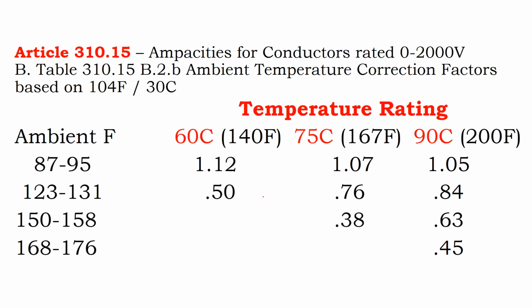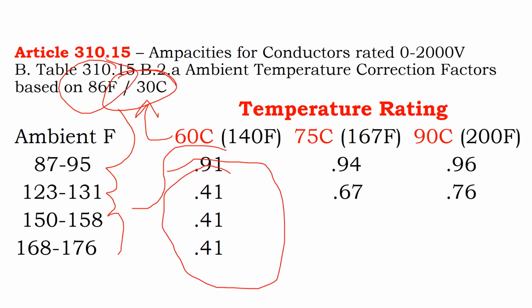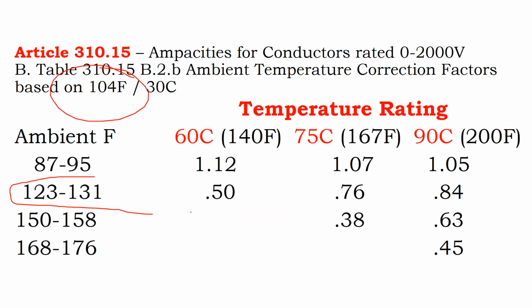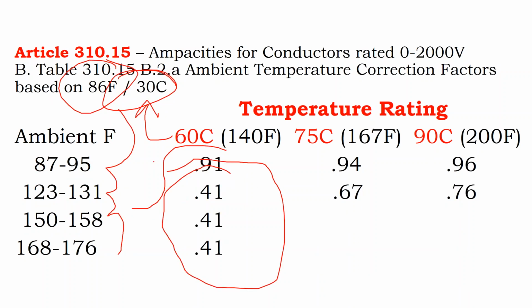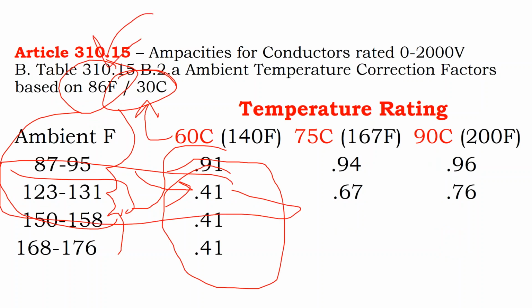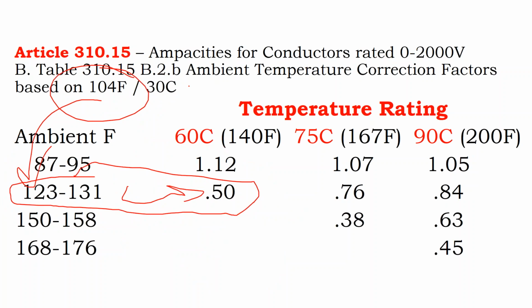Then we have the next table, and it's the exact same chart, but the only difference is it's done at 104 degrees ambient instead of 86 degrees ambient. So if you're trying to correct it for your actual ambient, now we're a little bit above it, and we have to derate the ampacity by 50%, whereas if we were doing our calculation based off a lower ambient, we would be derating it by 40%. The important thing is that you're being consistent with your ambient temperature. If I'm designing for an 86 degree ambient temperature, that's different versus 104 degrees. We're already factoring in additional temperature into the front side of the calculation, and so you get a little bit more leniency on the correction factor.